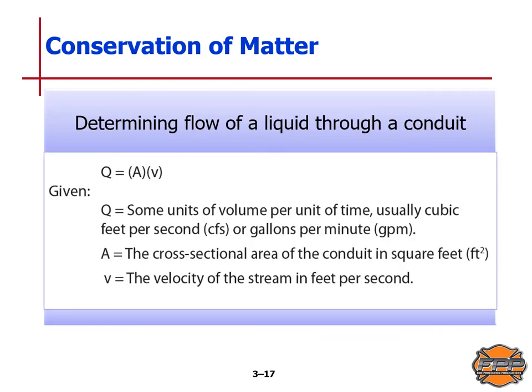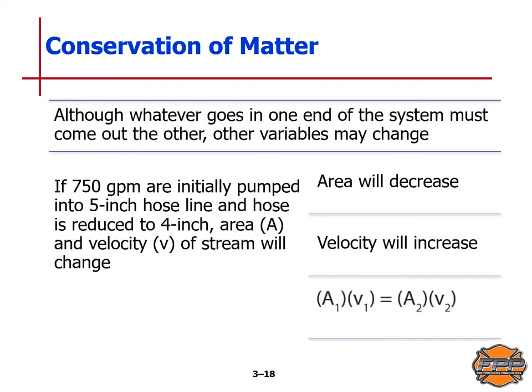Flow of liquid through a conduit is determined by Q equals A times V, where Q is volume per unit of time (usually cubic feet per second or gallons per minute), A is the cross-sectional area of the conduit in square feet, and V is velocity in feet per second. Although whatever goes in one end must come out the other, other variables may change. If 750 gallons per minute are pumped into a 5-inch hose line reduced to 4-inch, area A decreases but velocity V increases.